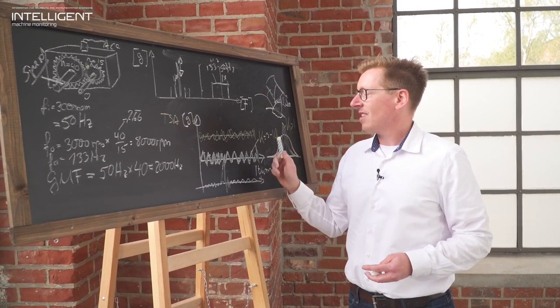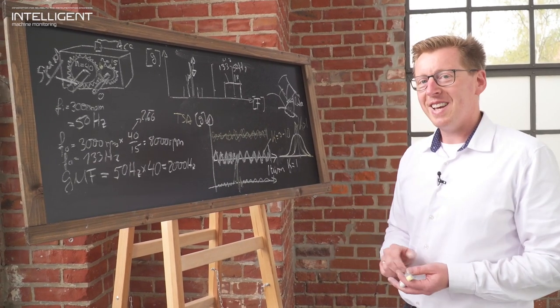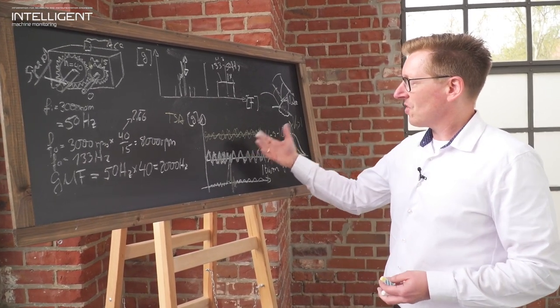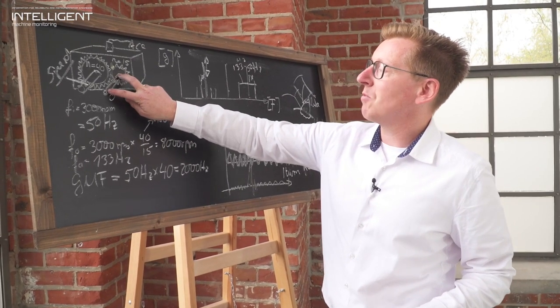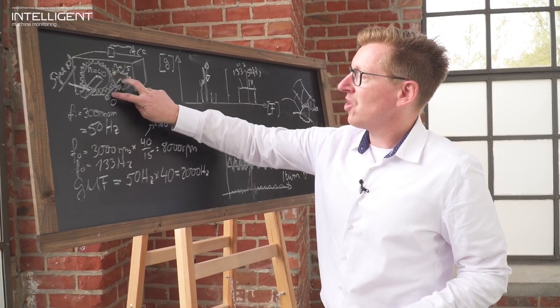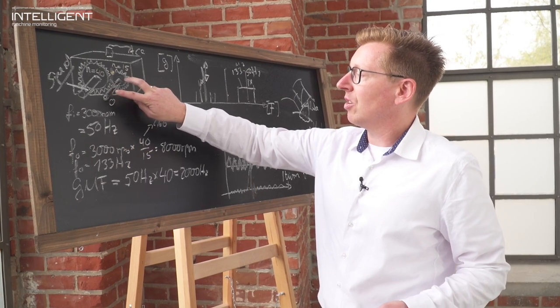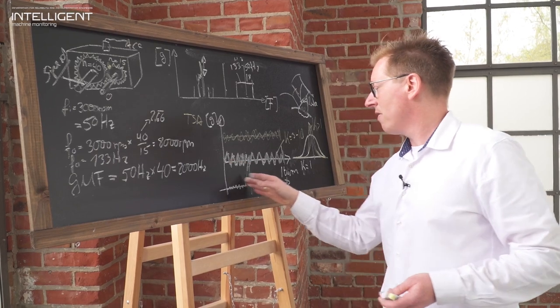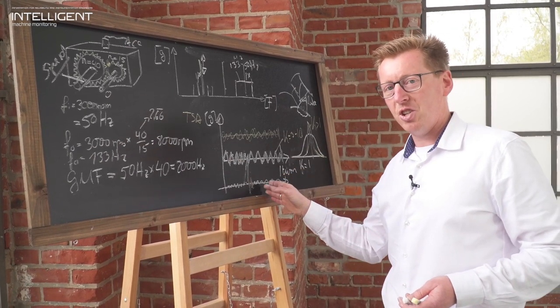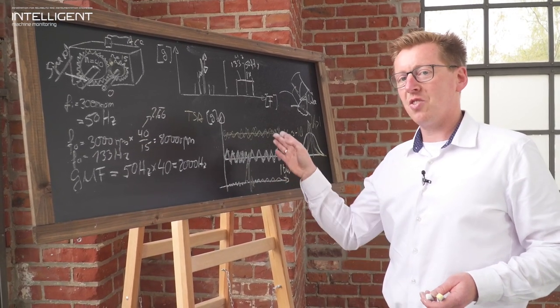Two more comments, two words of caution with the TSA. The kurtosis is sensitive to everything that happens in a synchronous way that is time synchronized to this shaft. If you are driving equipment that also produces synchronous impacting, these will also be visible in the time synchronous averaging, so this needs to be taken into consideration in the baselining.